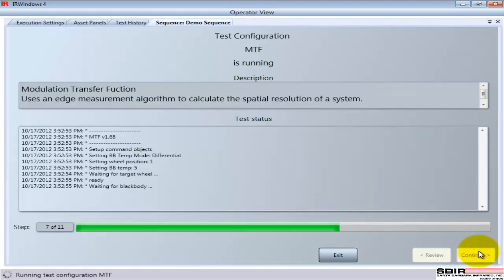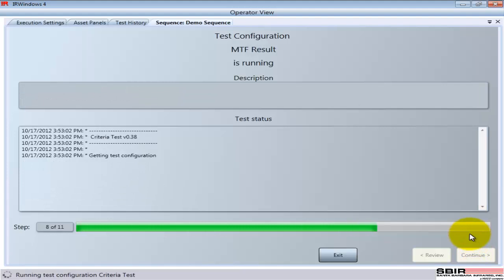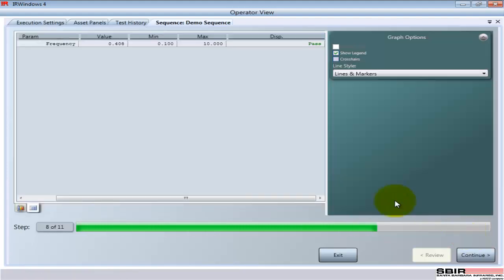And then the next test is an MTF, a focus test. In this case, we're actually controlling temperature of a blackbody, the target that's presented, collecting an image from the device, and analyzing that image. Again, we show the result and the fact that it passes.